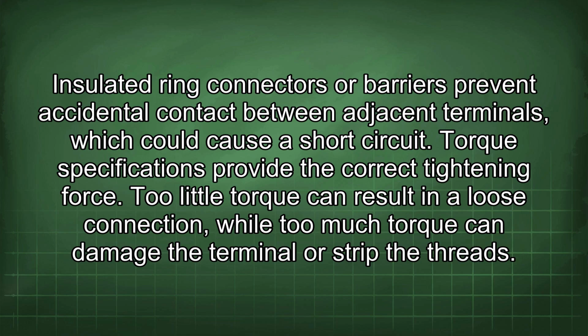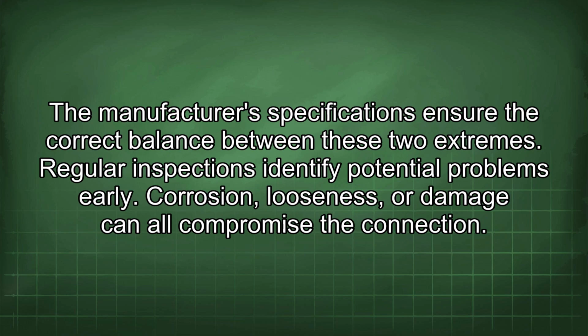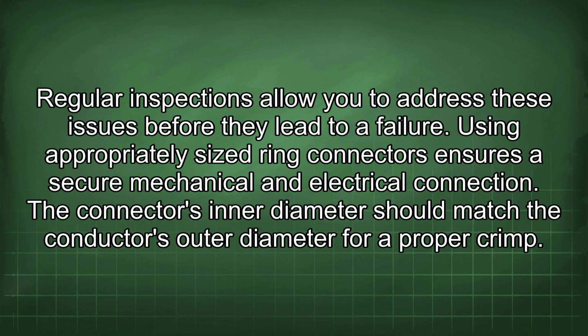Torque specifications provide the correct tightening force. Too little torque can result in a loose connection, while too much torque can damage the terminal or strip the threads. The manufacturer's specifications ensure the correct balance between these two extremes. Regular inspections identify potential problems early. Corrosion, looseness, or damage can all compromise the connection. Regular inspections allow you to address these issues before they lead to a failure.